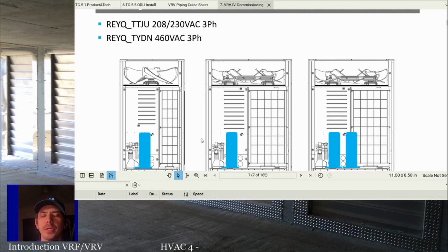On a heat recovery, you're going to have 3 pipes. So real quick now, the 3 pipes are liquid line, low pressure gas, and high pressure/low pressure gas. So you always have a liquid line no matter what. You have a low pressure gas, which is your suction line, and you have high pressure gas, which is discharge. But that third line can also double as an extra suction line. So on very hot days where everything's running full tilt in AC, you'll basically have 2 suction lines. Any other time, the discharge line goes inside to be able to provide heat if heat's needed anywhere, and then your other lines are for cooling. You will always have at least liquid and suction, and then discharge or an extra suction.